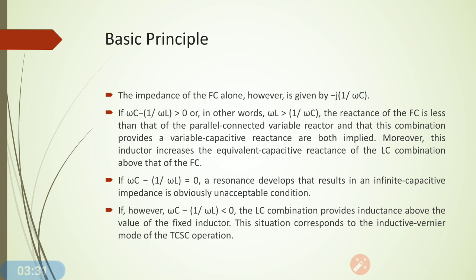There are three conditions in which we can analyze this TCSC. The first condition is when the reactance of the fixed capacitor is less than that of the parallel connected variable reactor. In this condition, the LC combination provides a variable capacitive reactance. The inductor increases the equivalent capacitive reactance of the LC combination above that of the fixed capacitor. In this mode, the TCSC basically works as a capacitor.